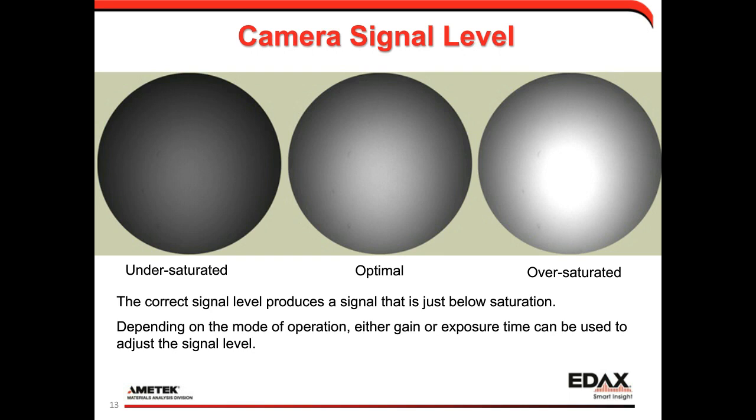If you optimize your camera in an area that has a lower level and move the camera to a higher level, you can oversaturate your image. That's what we're trying to avoid by keeping it down to 0.85 instead of 1. Because 1 would be what we really want, but again, your sample isn't usually uniform enough for that to happen.